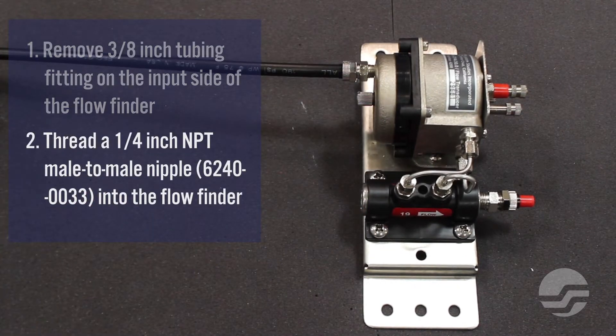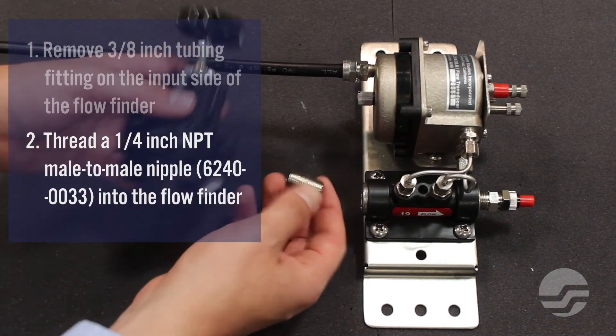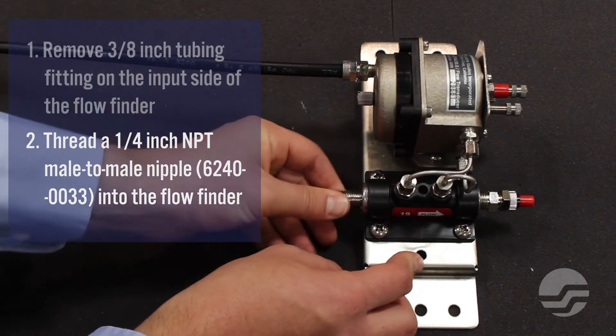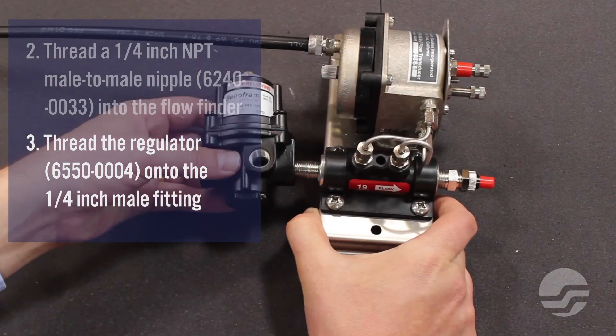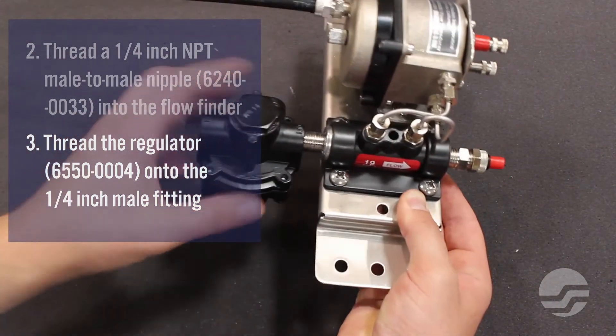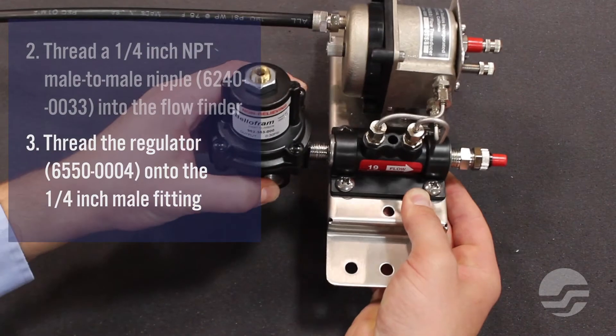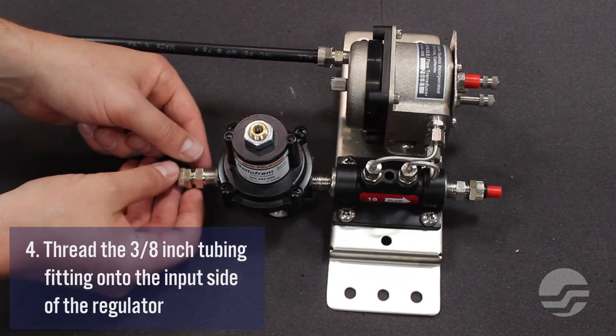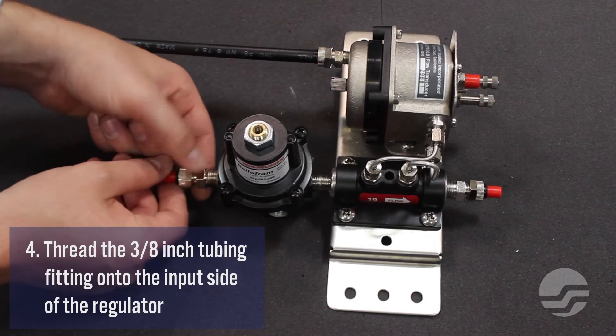Thread a 1/4 inch male-to-male nipple into the flow finder. Next, thread the regulator onto the 1/4 inch male fitting. Finally, thread the 3/8 inch tubing fitting onto the input side of the regulator.